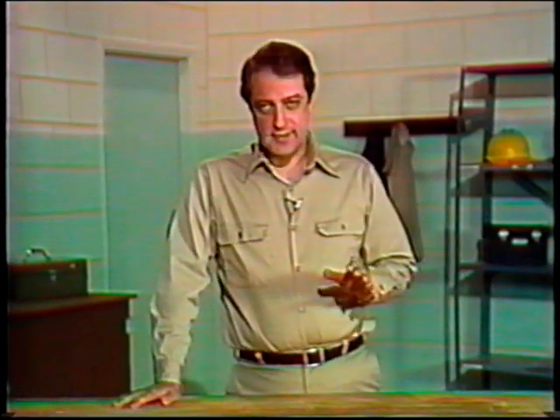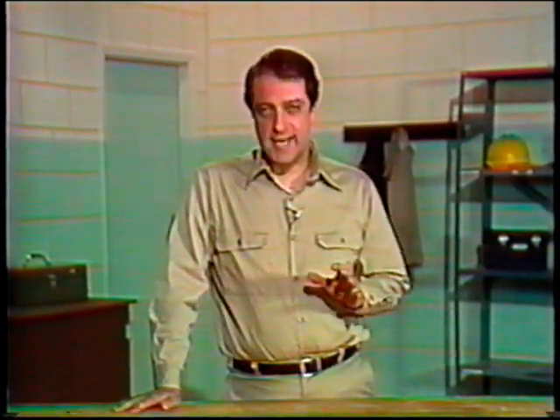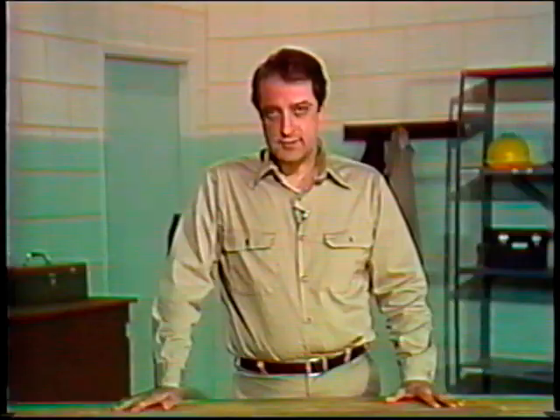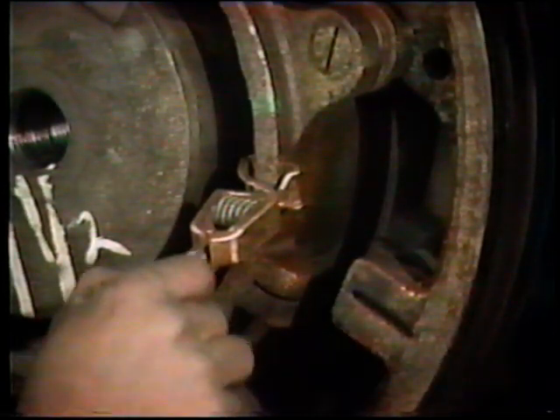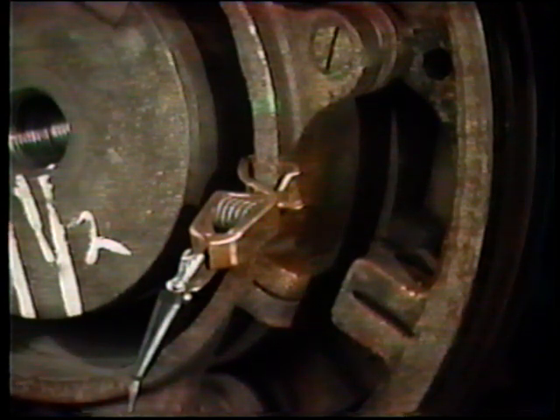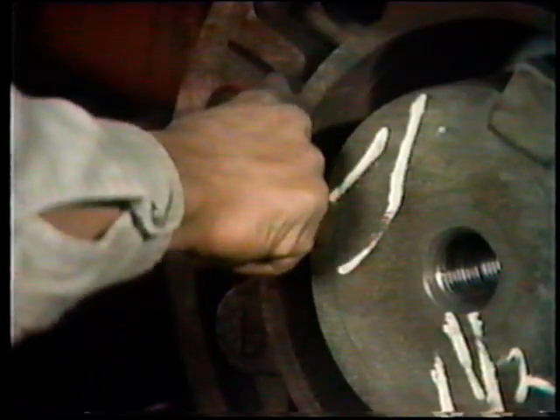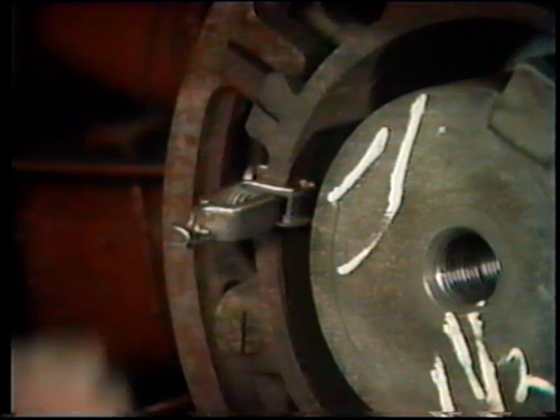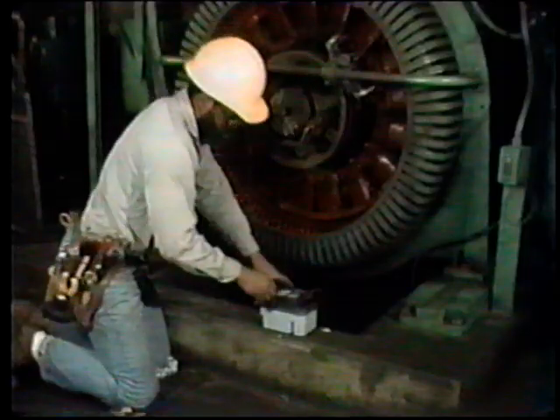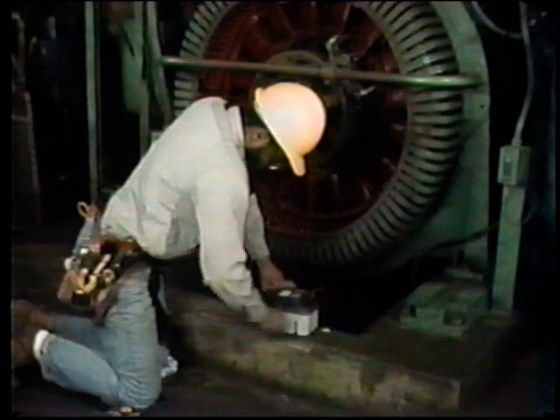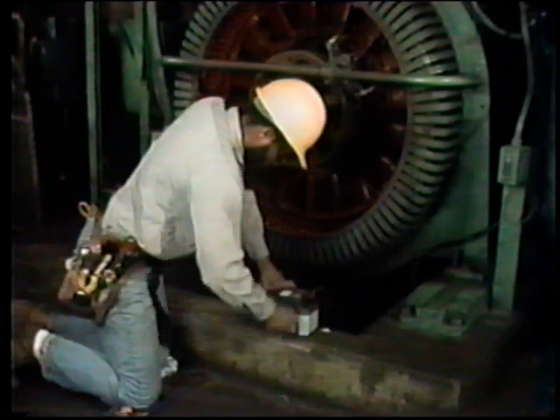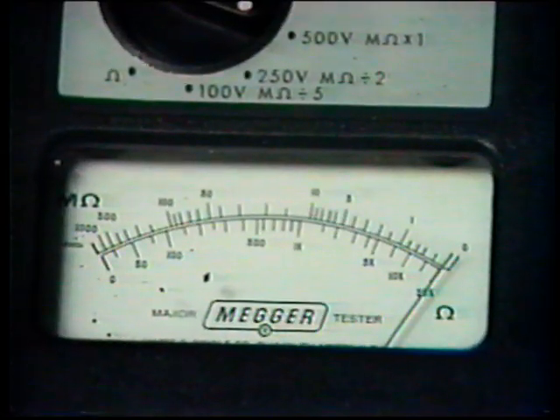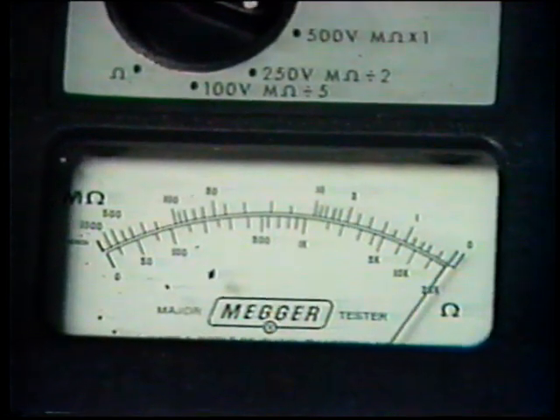Before beginning the insulation test, the meg-ohm meter should be tested. Using proper procedures, make sure it will indicate infinite resistance and zero resistance. Next, attach a clip to the motor's shaft and connect the meg-ohm meter's ground lead to the clip. Then attach another clip to the shaft and connect the line lead to it. Operate the meg-ohm meter. It should indicate zero resistance. This means the ground connection is good.